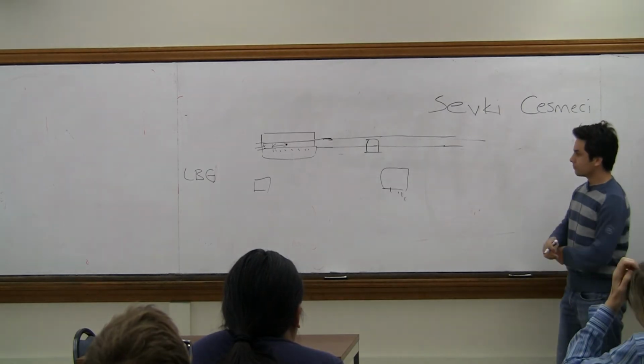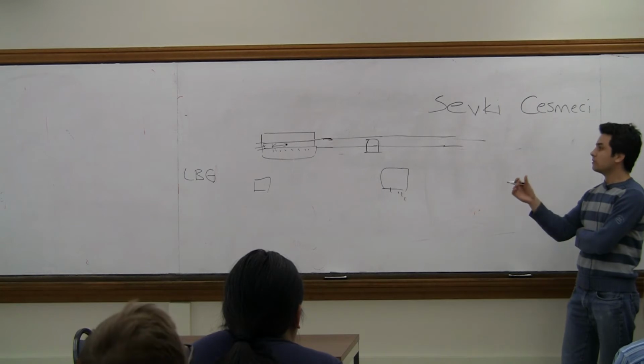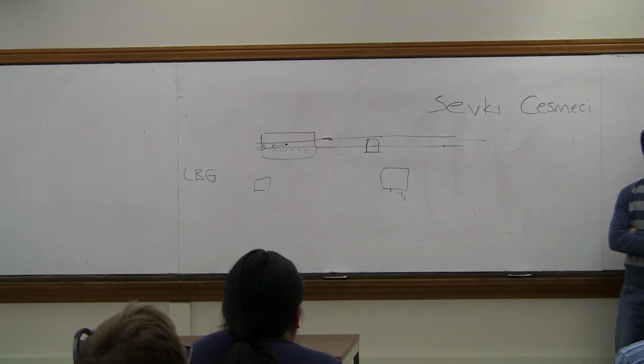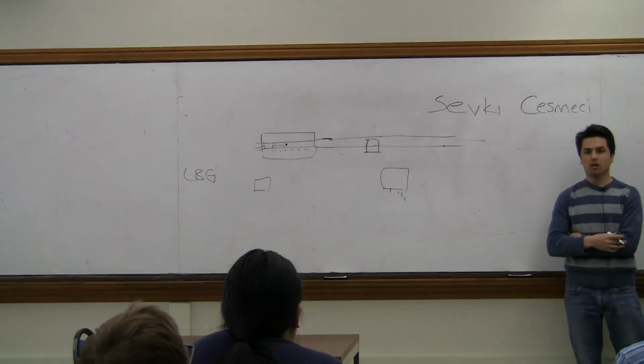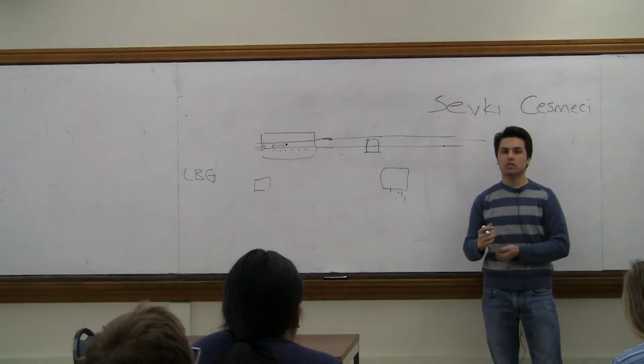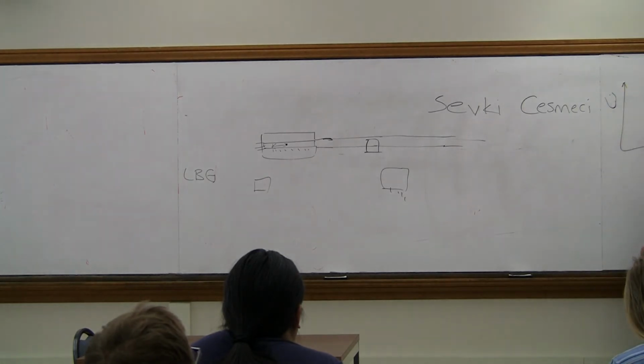We also, as I said, send different types of flow patterns, like a single cough or a triple cough, or a single cough with oscillations. Single cough would be, let's say this is volume flow rate, and this is time. A single cough would be a cough pulse, something like this.